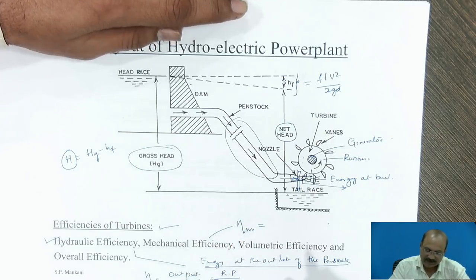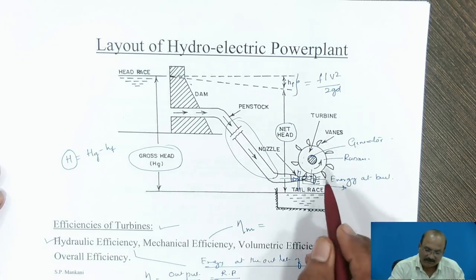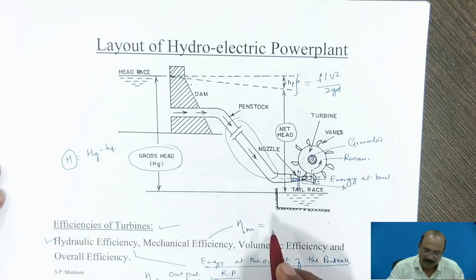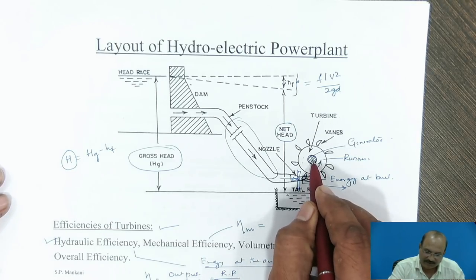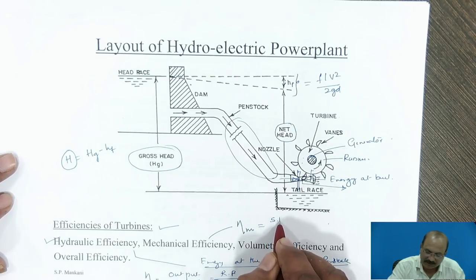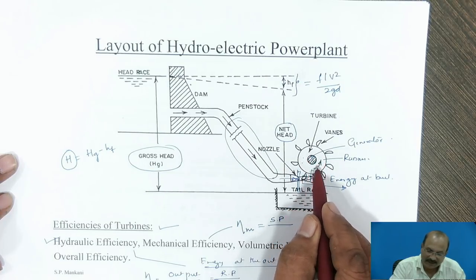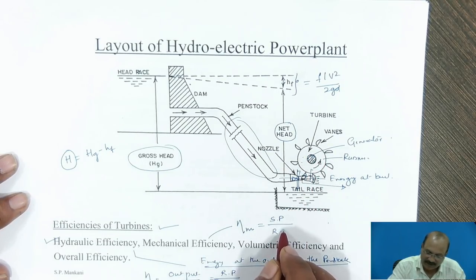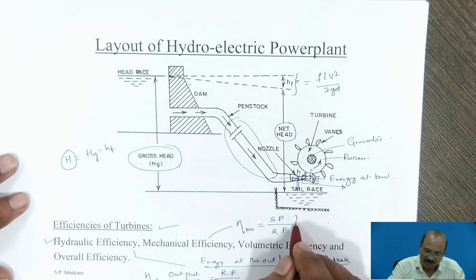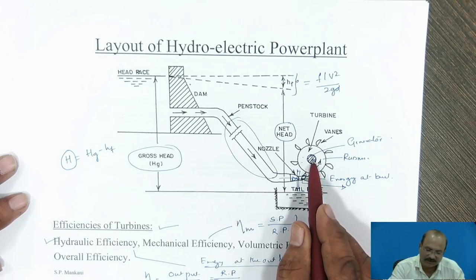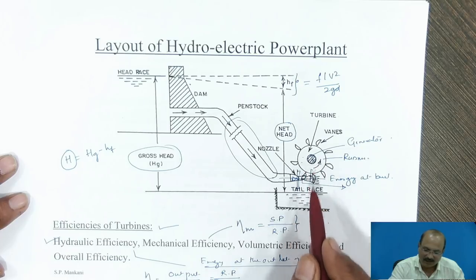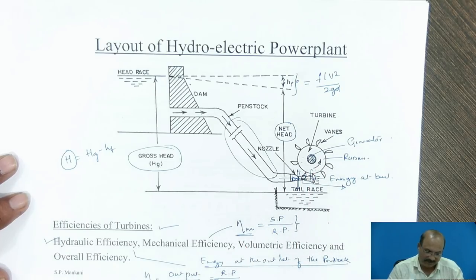Next is mechanical efficiency. Mechanical efficiency is explained as the power available at the runner compared with the power available at the shaft. The output is the shaft power, so mechanical efficiency equals shaft power divided by runner power. This is because the total energy available at the runner is not fully transferred to the shaft — there will be mechanical losses represented by mechanical efficiency.